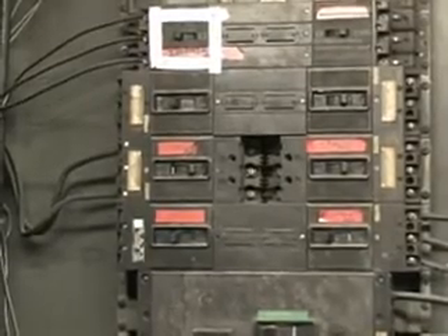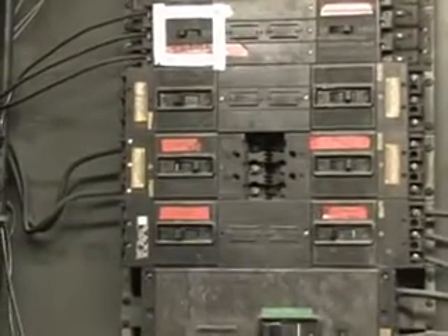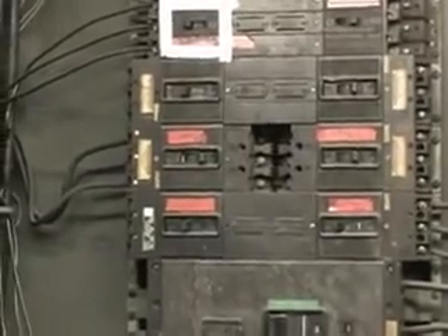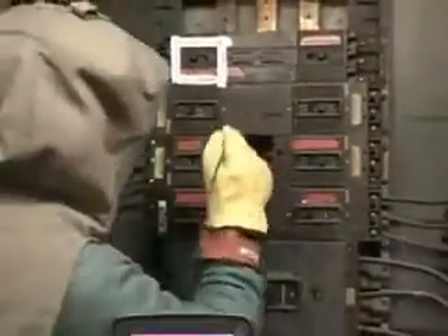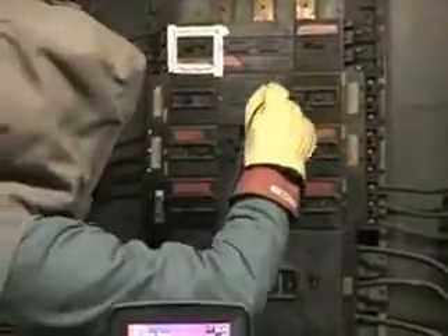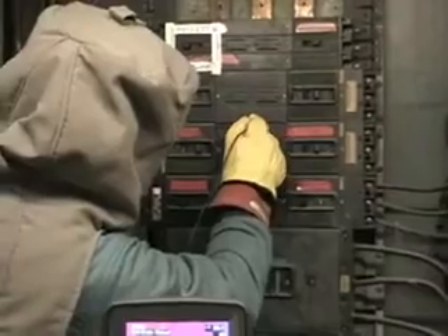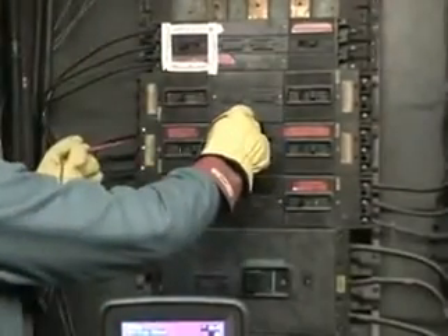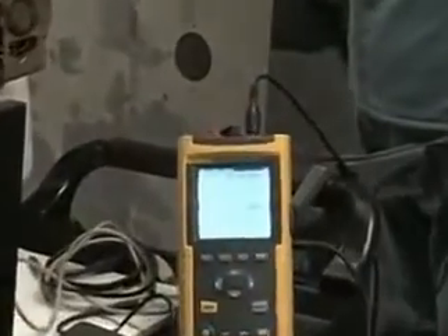This clearly identifies the true benefit of ultrasonic testing. The noise identified within the breaker is not generating any significant amount of heat, and therefore would go undetected by the camera. The noise does indicate that the contacts within the breaker are deteriorating. We'll verify this by taking a millivolt drop test across each adjacent pole of the breaker.